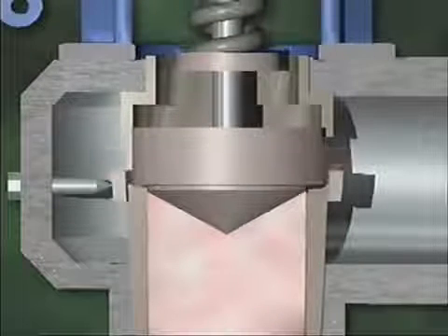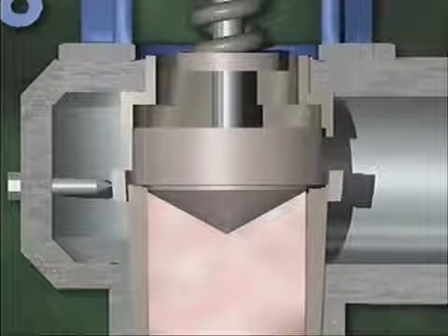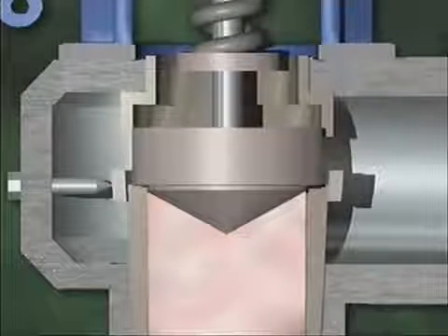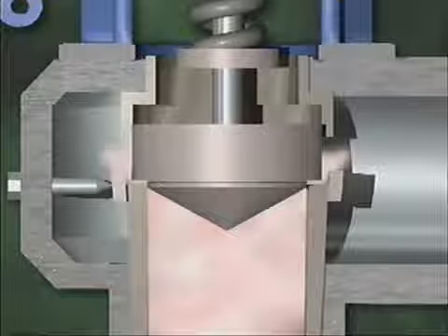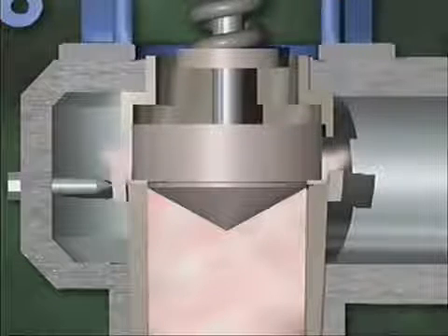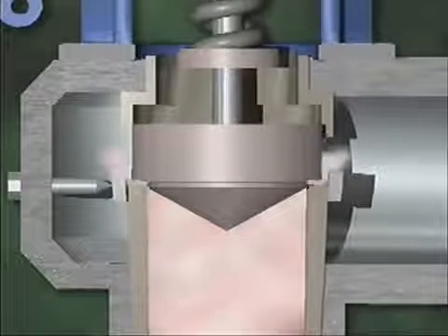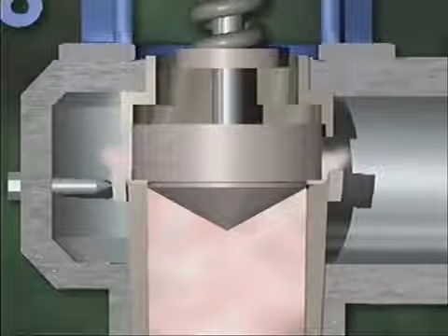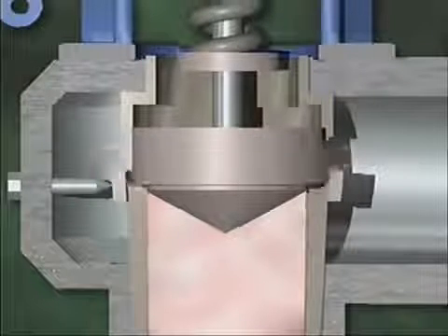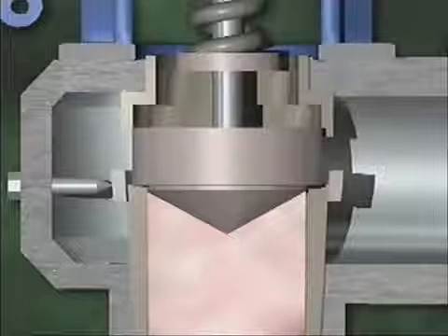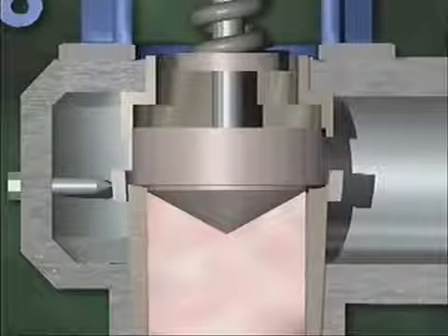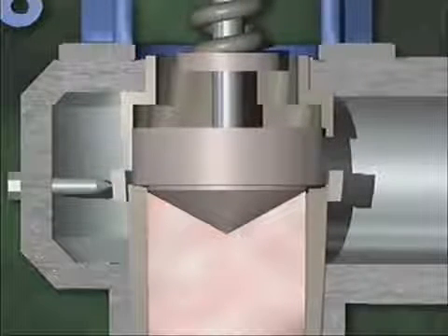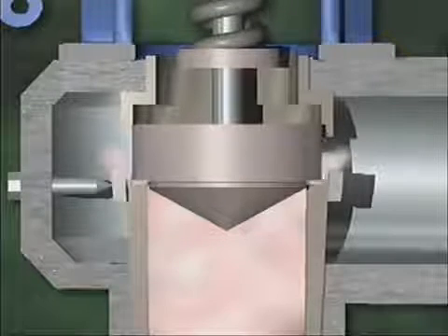Adequate blowdown helps prevent a condition called chattering. You see, if there's no difference between a valve's popping pressure and its seating pressure, the valve disc will jump up and down on its seat until pressure either increases enough to pop the valve open again or decreases enough to keep it closed.